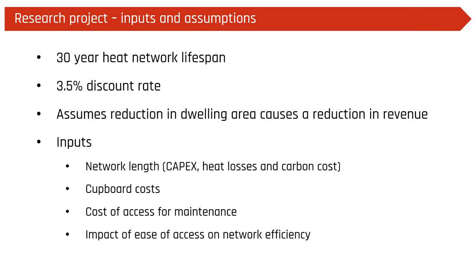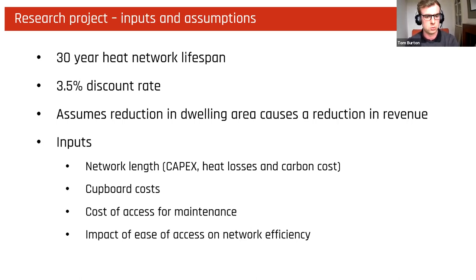So now going on to the research project that I ran. As I mentioned, it's a net present value study, looking at the life cycle costs of externally accessible HIUs and comparing that to the conventional network layout that we saw at the start of this presentation. I did that over 30 years with a 3.5% discount rate, assuming that any reduction in dwelling area would cause a reduction in revenue from sales. The main things we were looking at were the network length from a capex, heat loss, and carbon cost perspective. Then also the cupboard cost, so the extra insulation, doors, locks, and longer connections between the HIUs and the flats. And then the cost of access maintenance and the impact of the ease of maintenance on efficiency.